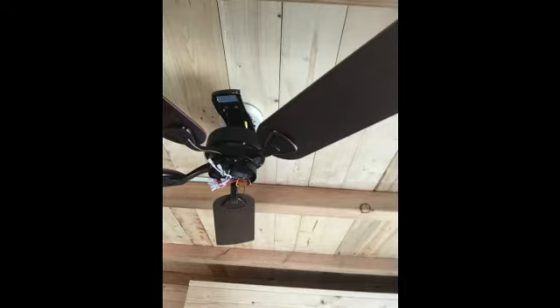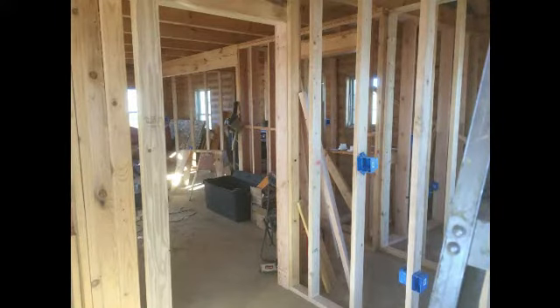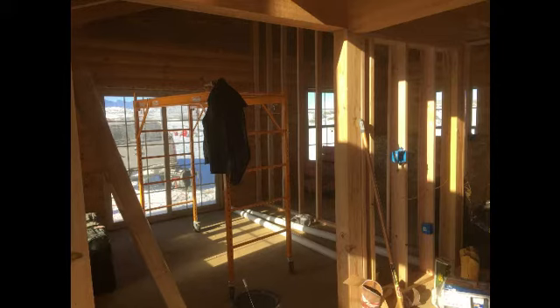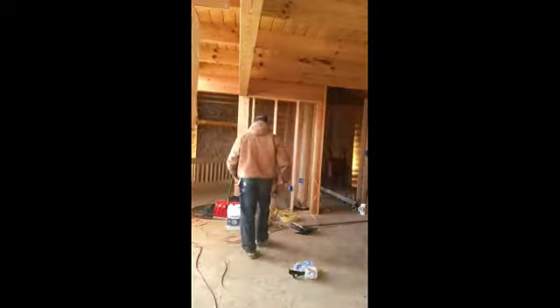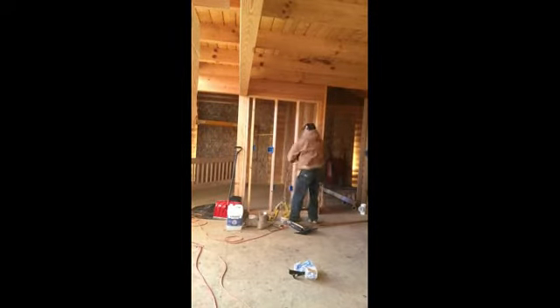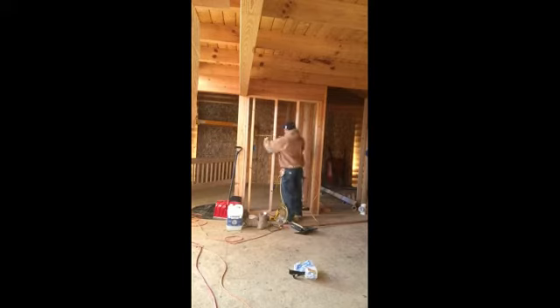Step 2, you're going to be nailing in electrical boxes. Of course, your electrician will do this. First, you're going to want to start in one room. Let's select, for instance, the master bedroom, and nail into the stud. Place boxes about 14 inches from the OSB subfloor. Except in areas like kitchen countertops and bathrooms, you don't need to have the plugs that close to the floor. You can have them up above the counters. And in garages as well, you can have them on your workbenches.